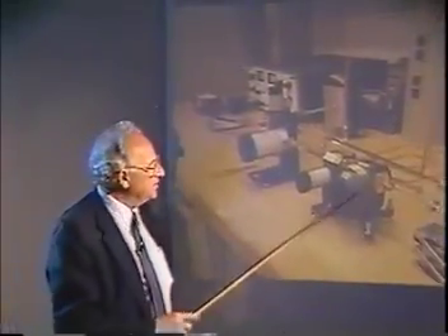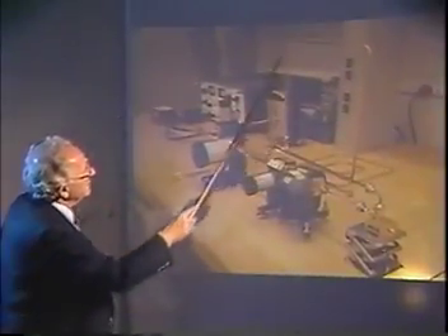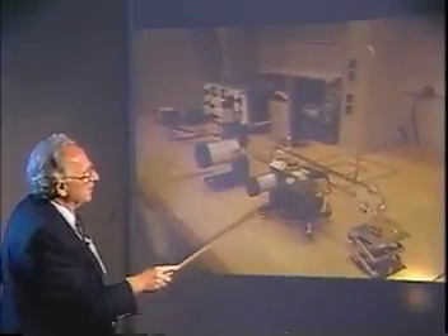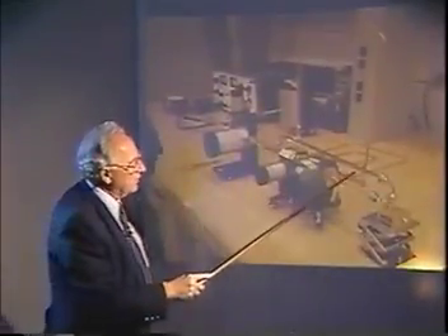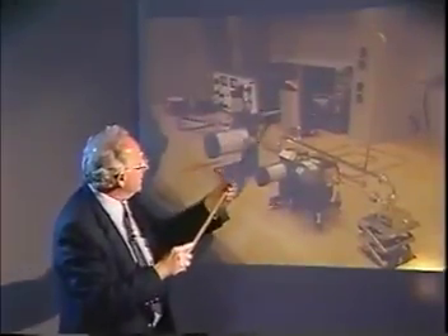Many, many rings of that black cable on the bench. This is at 94 gigahertz. Notice this delay line is only this long here. Now this one, this long one here, you see, is so you can get in close to the carrier. Then when you're going out further from the carrier, you can put in these shorter delay lines here. So then you'd have a calibration in close to the carrier down, say, like this.